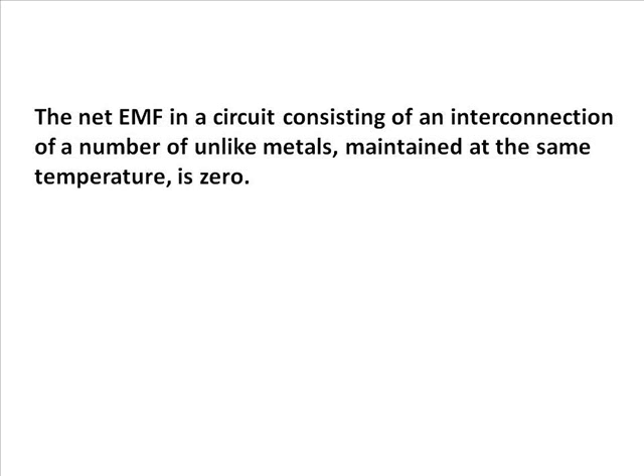That means if other metal conductors are inserted in the thermocouple circuit and the junctions of these interconnected metal conductors are at the same temperature, then the output EMF will not be affected and remains the same as if it was made of only two metals.